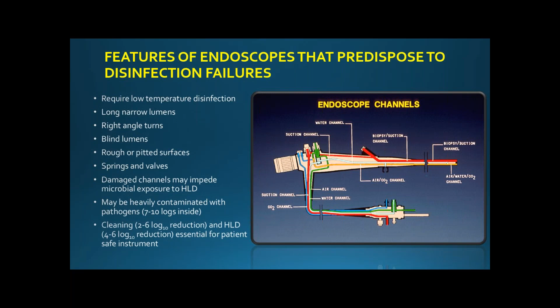Endoscopes, by design, are at high risk of failure when it comes to cleaning and disinfection. Again, it requires low temperature disinfection. They have long, narrow lumens. All those right angles make it very challenging to get things through and around the corner and to clean appropriately. And there's the amount of heavy contamination. So endoscopes are not really designed for easy cleaning and disinfection, which is another reason why some places have been going to disposable scopes. There are a lot of different options anymore to try and combat these issues.